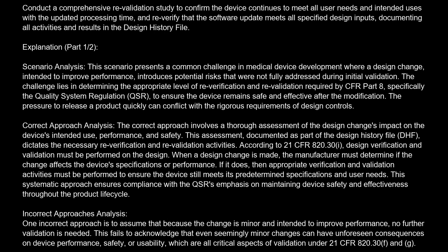Conduct a comprehensive revalidation study to confirm the device continues to meet all user needs and intended uses with the updated processing time, and re-verify that the software update meets all specified design inputs, documenting all activities and results in the design history file. Explanation.